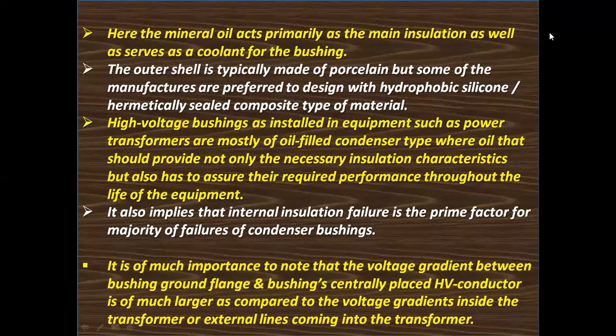Here, the mineral oil acts primarily as the main insulation as well as serving as a coolant for the bushing. That mineral oil is nothing but transformer oil. The outer shell is typically made of porcelain, but some manufacturers prefer to design with hydrophobic silicone or hermetically sealed composite type material. High voltage bushings, as installed in equipment such as power transformers, are mostly of the oil-filled condenser type, where the oil should provide not only the necessary insulation characteristics but also assure the required performance throughout the life of the equipment.